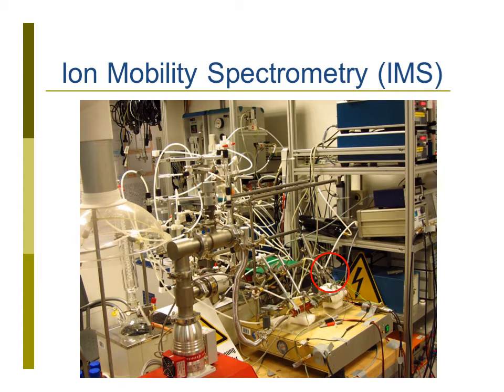There are voltages for the detector, there are high voltages, a few thousand volts for the device, and a few other voltages, and all the white tubes that you see here are just there in order to provide this device with gas, because it is a gas detector. You use ion mobility spectrometry to detect gases, and mainly this means identifying what gas is somewhere, so identification of unknown gases.